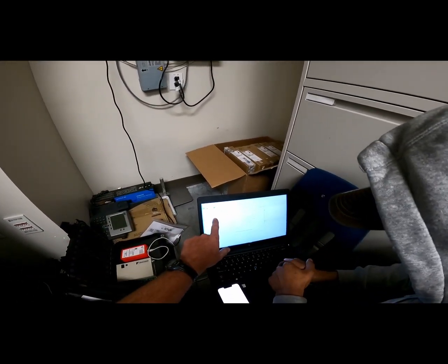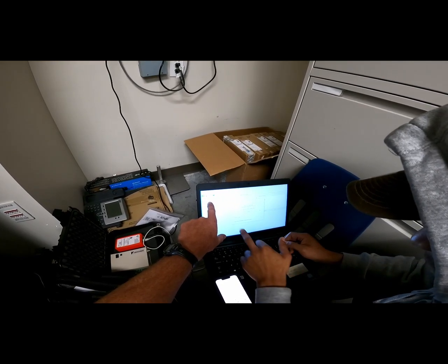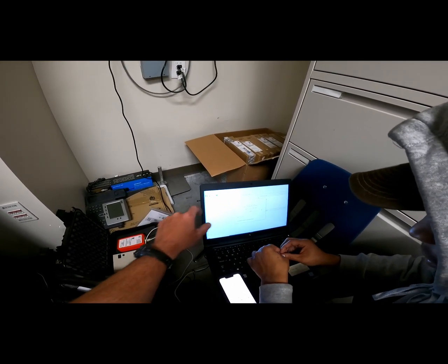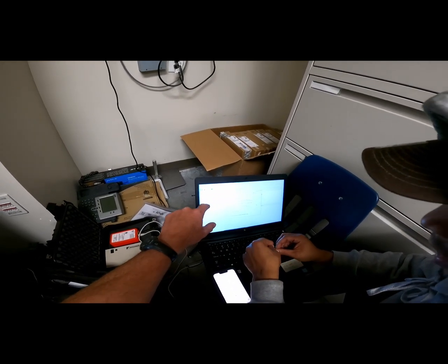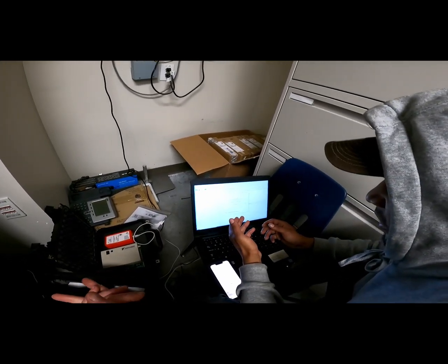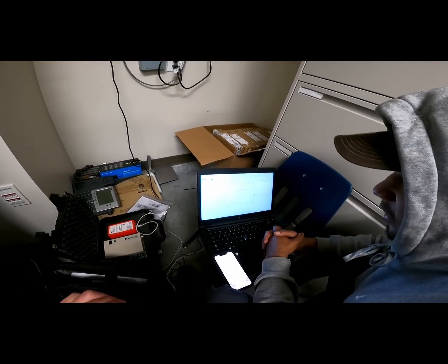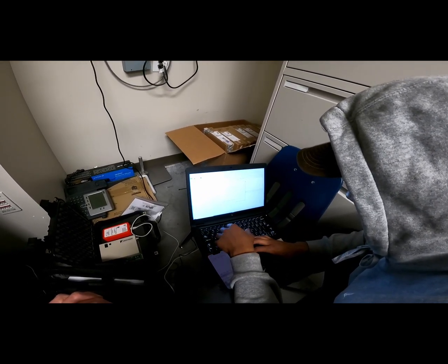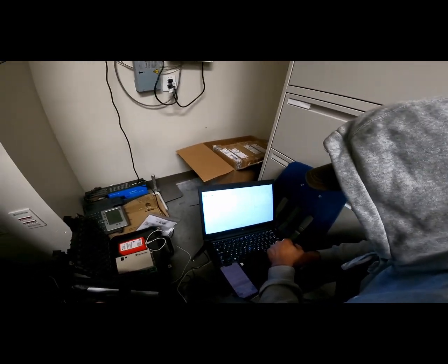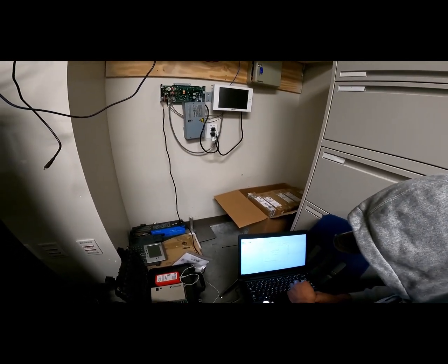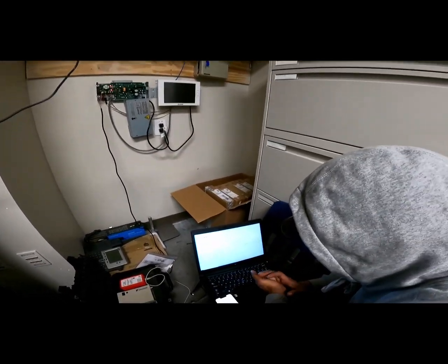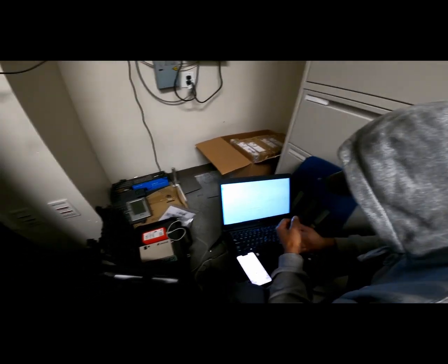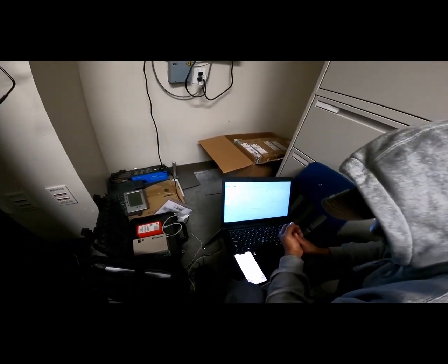Now I believe what's going on here, do you see how some of these, this IC stands for indoor coil, some of them are green and some of them are gray? Yeah. I believe the gray ones are inactive. No, that are inactive. The green ones I believe are running, the gray ones are inactive. Don't quote me on that, I'm not sure. And it's going to take quite a while to populate because there are so many units on the system.